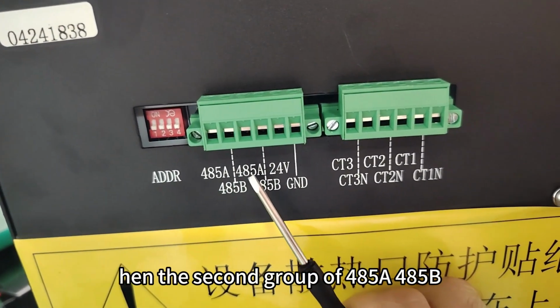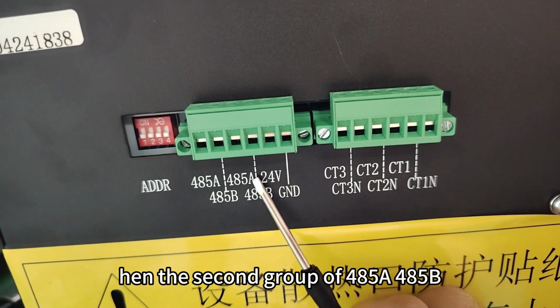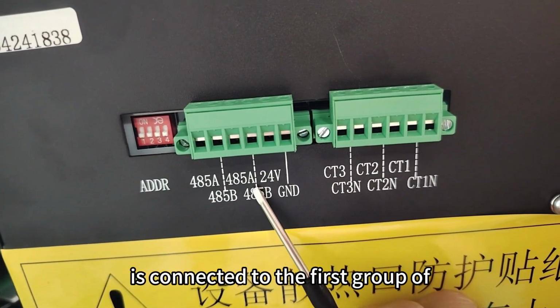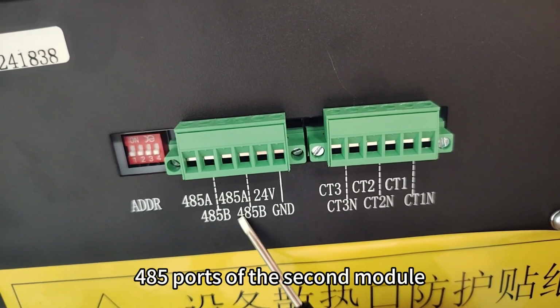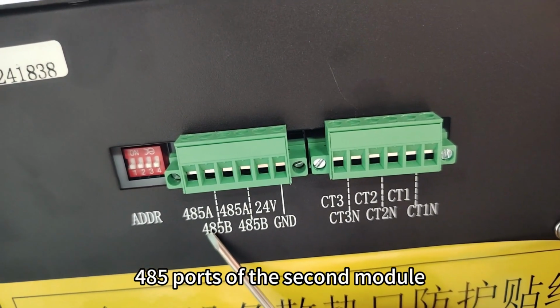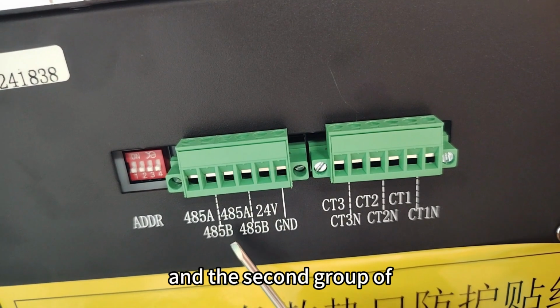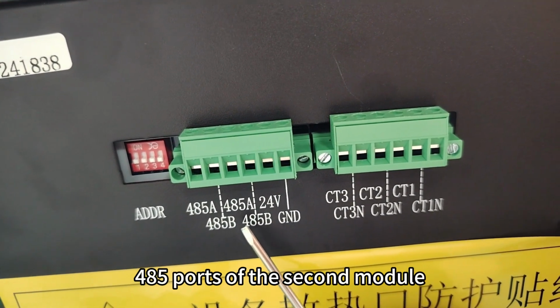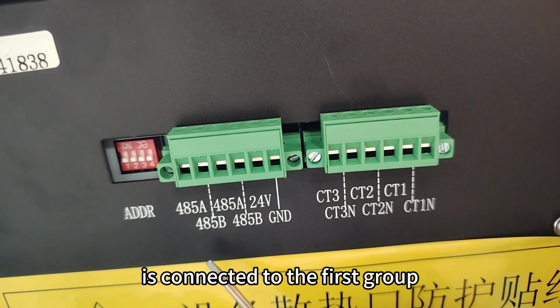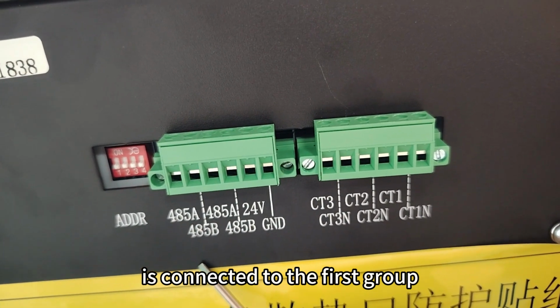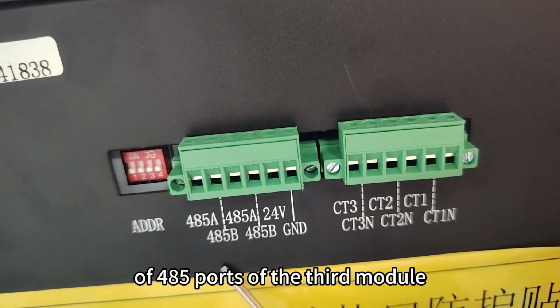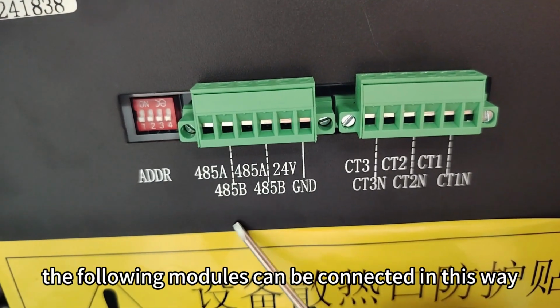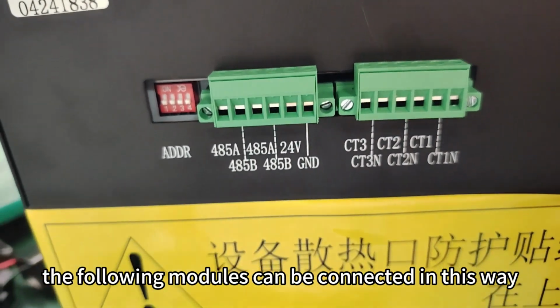When multiple modules are used in parallel, the control panel is connected to the first group of 485A, 485B of the first module. Then the second group of 485AB is connected to the first group of 485 ports of the second module, and the second group of 485 ports of the second module is connected to the first group of the 485 ports of the third module. The following modules can be connected in this way.